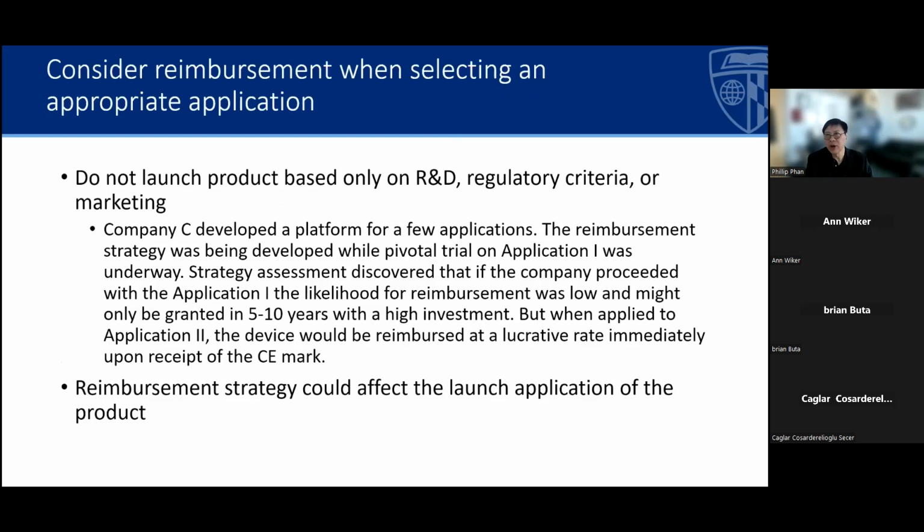You don't have to do that for every device. Certainly, if it's an invasive device, you can't sell it without FDA clearance. But if it's something fairly benign and low risk, a lot of companies will want a 510(k) because it's a marketing or branding thing. That's fine.